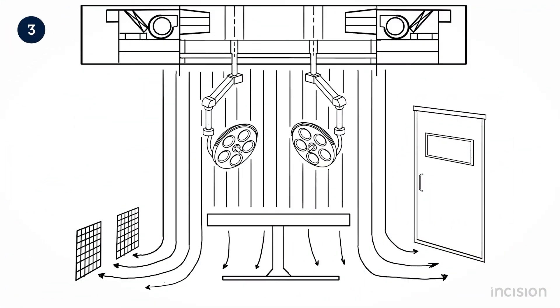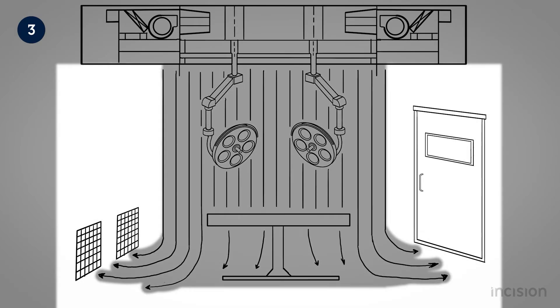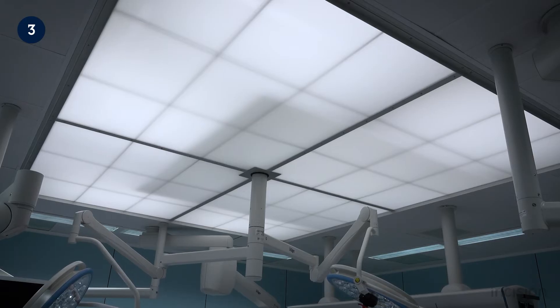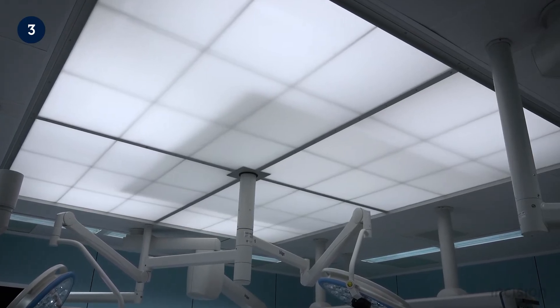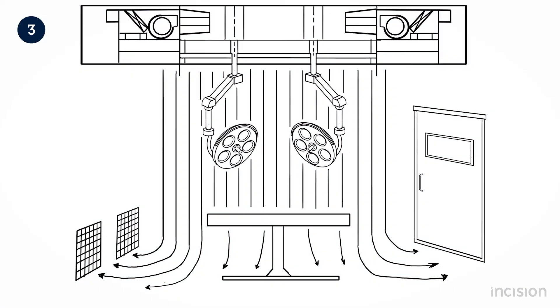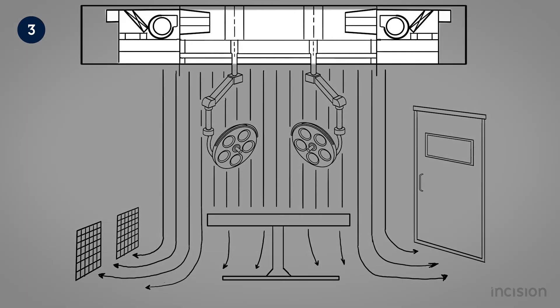To control bioparticulate matter in the operating room, a specialized ventilation system has been developed. It is usually located in the center of the ceiling, right above the surgical table, and is designed to provide a clean, filtered downflow of air while displacing the ambient air in the room. This prevents particles from moving towards the sterile area and is known as laminar downflow. A laminar flow diffuser panel concentrates and directs a downward airflow, displacing polluted ambient air with an invisible column of cool, filtered clean air. Vents located in the walls provide active extraction, directing air via the return air zone into advanced filters above the ceiling.